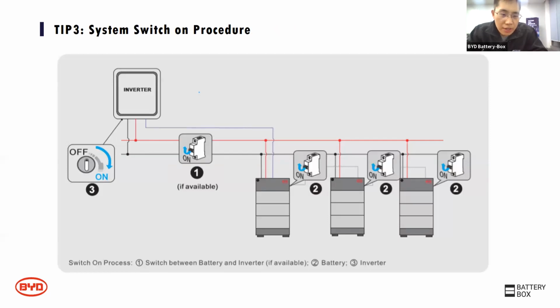Tip 3 is the switch-on process. When you install the systems and turn them on, please always make sure, firstly, to switch the circuit breaker if you have one. That's number 1. Number 2, always turn on the battery before the inverter. The third step is to turn on the inverter. So the recommendation is: always turn on the battery first, then turn on the inverter.